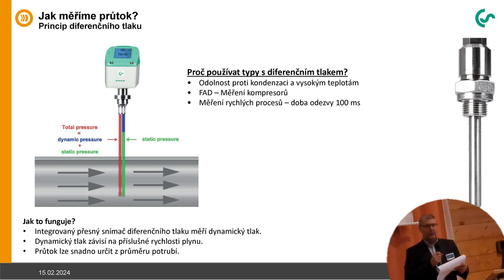How does it work? So the sensor has internally a precise differential pressure sensor, which measures the dynamic pressure, which is, let's say, the difference between the total pressure and the static pressure. And the dynamic pressure corresponds to the air velocity inside the pipe. So it's a quite common way to measure the volume flow.